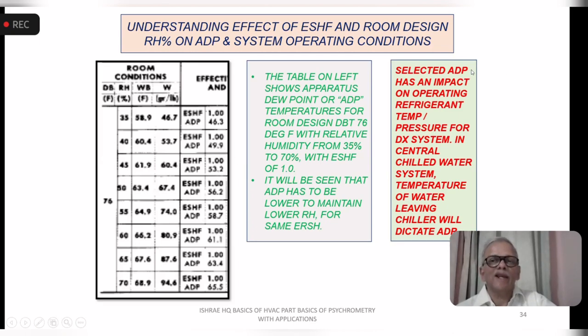So the selected ADP has an impact on the operating refrigerant temperature and corresponding pressure for a DX system or a chilled water system, which will be much lower. So it is important to know what the ADP is, or what the surface temperature of the apparatus is, to ensure that you are maintaining the desired quality of air to be supplied.